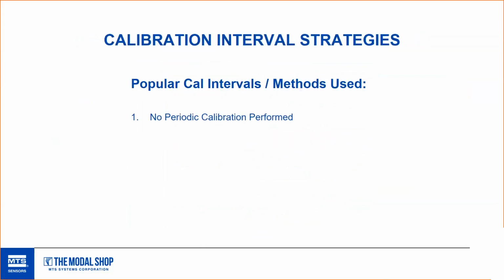With popular intervals, like no periodic cal performed, that's fine. It's really great for sensors that don't make measurements, display units, demo units, or something that might show a level of performance, but the accuracy of data isn't important. It can also be used if the measurement instrument is unlikely to change. Think of something like a standard desk ruler. It's not likely that the ruler is going to drastically change, so perhaps no periodic calibration is a fine strategy.